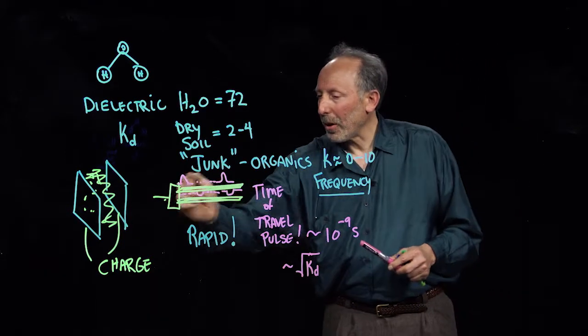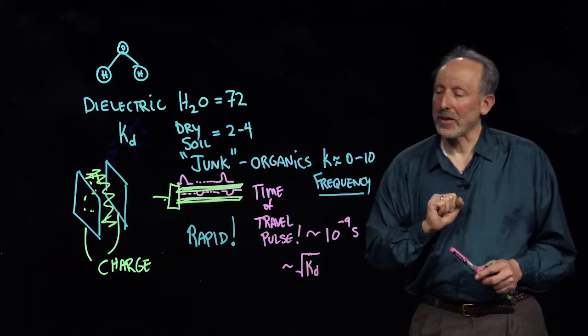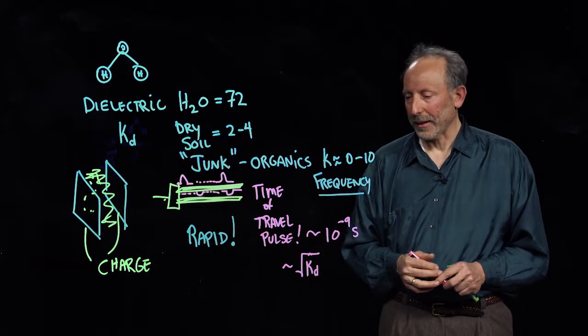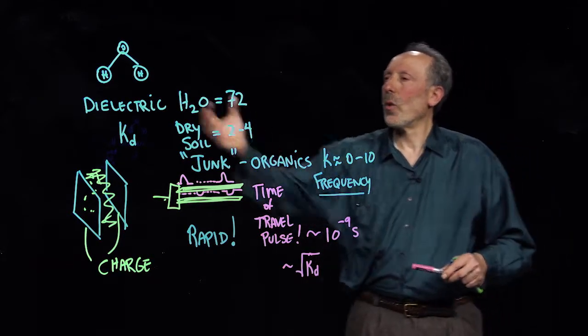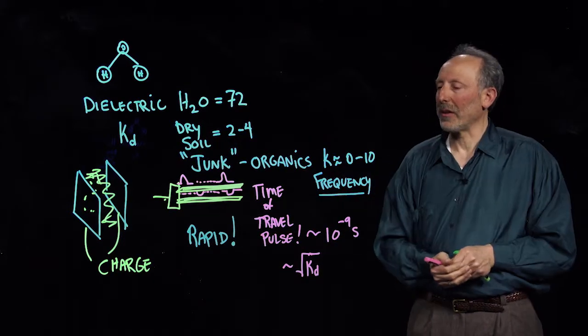It turns out that the time of travel is proportional to the square root of the dielectric. We insert a pulse, see it go down, see it come back to our instrument, and report that amount of time. The longer it takes, the higher the dielectric, because the water has to reorient and that slows the movement of the electric signal down.